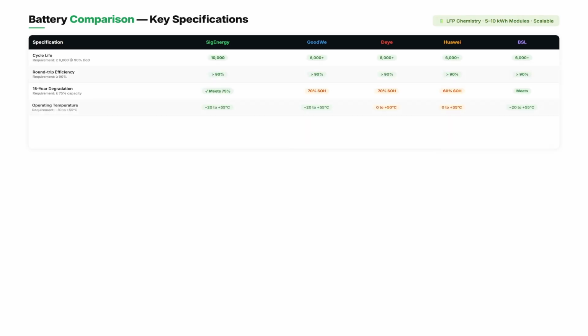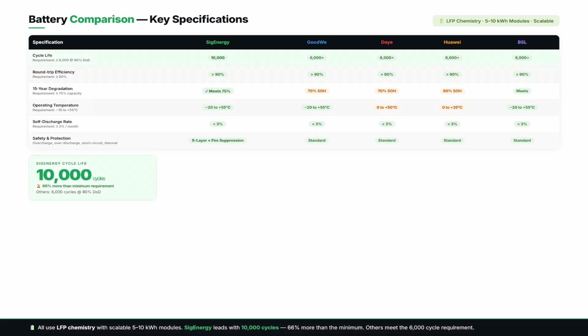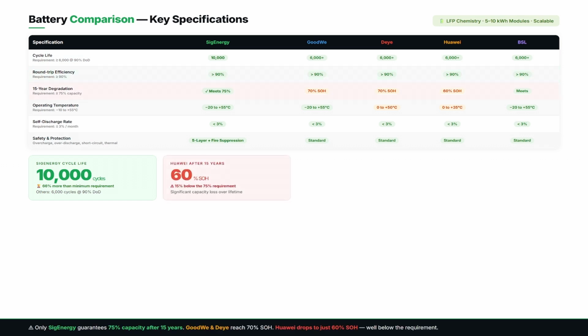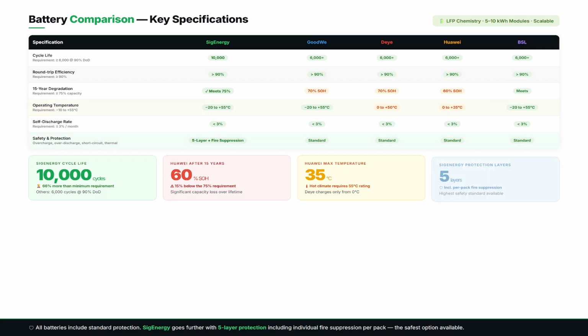All of these batteries are LFP with 5 to 10 kilowatt hour modules, scalable for future expansion. All have 6,000 life cycles at 90% DOD, except SigEnergy, which has 10,000 life cycles. It is required to remain at 75% of total capacity after 15 years of linear degradation, and only SigEnergy can meet this. Except for that, others can operate from -10 up to 50-55 degrees Celsius. The self-discharge of all is below 3%. All have protection against overvoltage, overdischarge, short circuit, and thermal protection. And SigEnergy also has more protection and safety on the batteries.